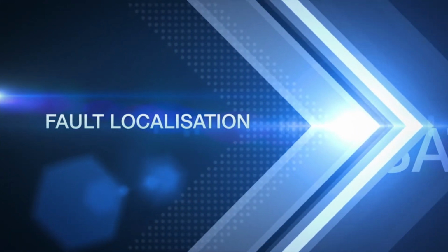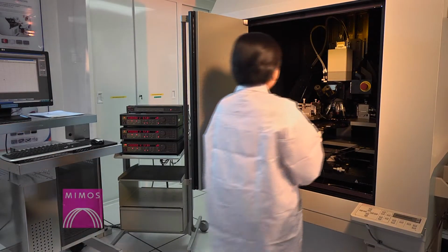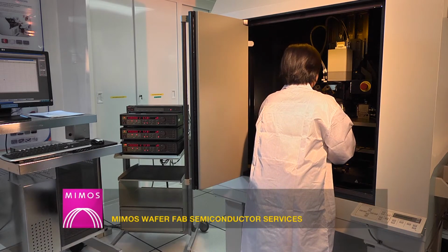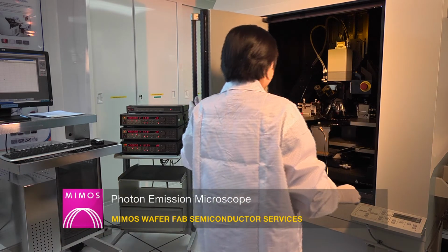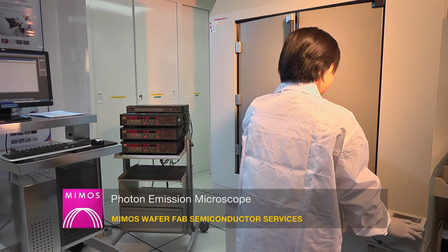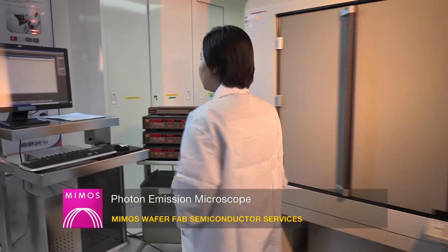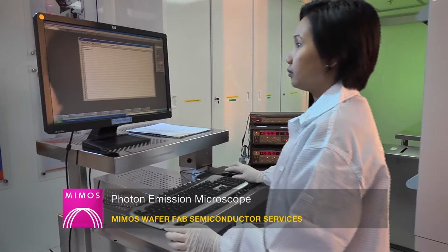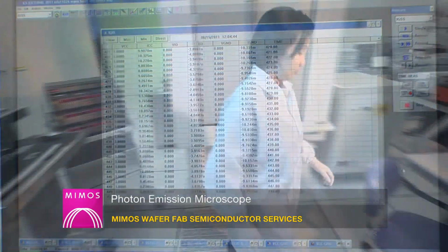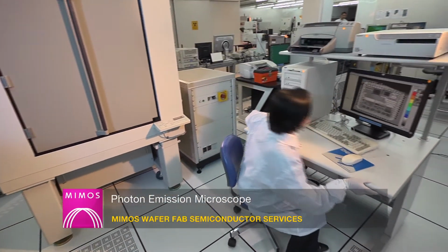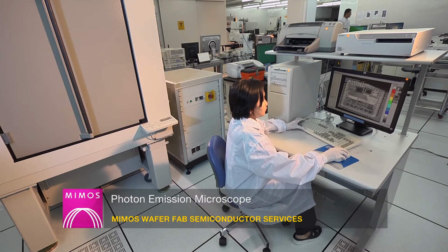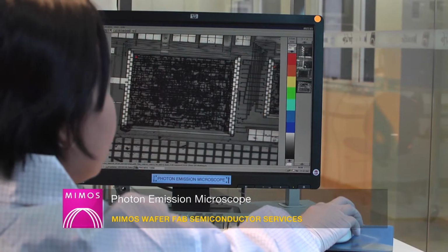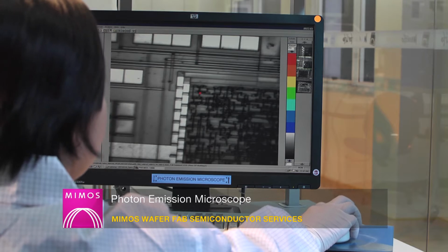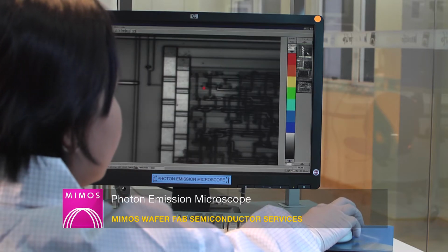Fault localization is an important step to pinpoint or localize the failure site. Photon emission microscope uses photon emission detection technology to localize leakage current defects at die level. Equipped with an indium gallium arsenide camera, PEM is capable of locating very faint photon emissions in all ranges from the visible to the near infrared region (NIR).